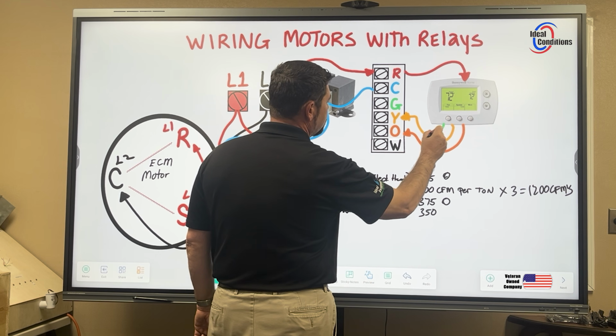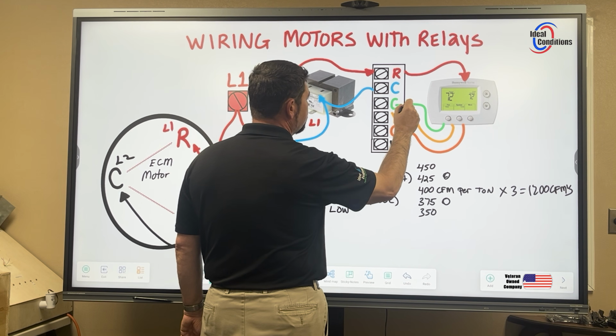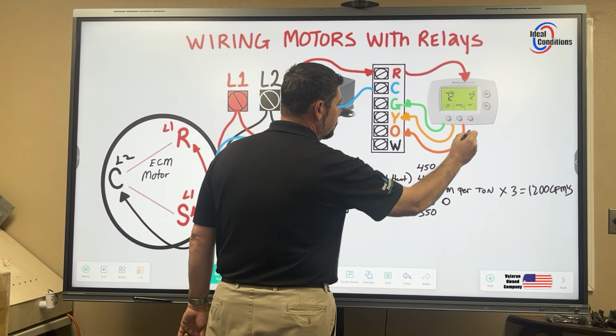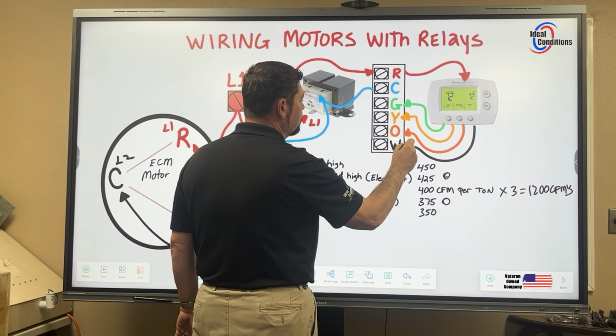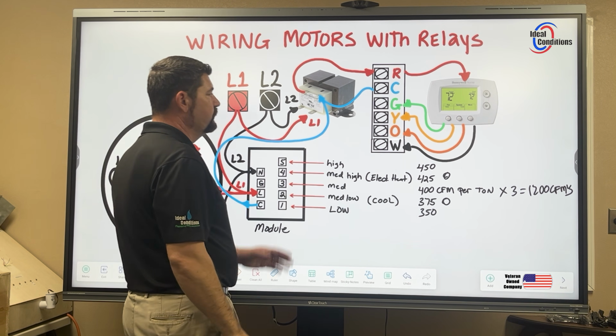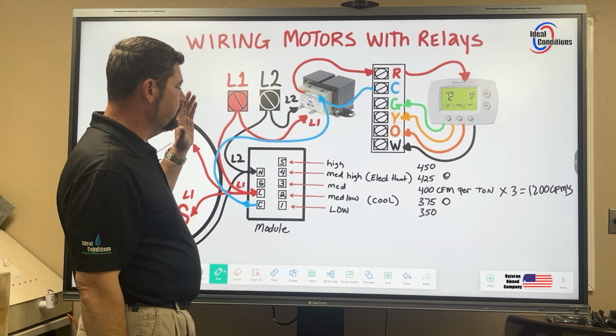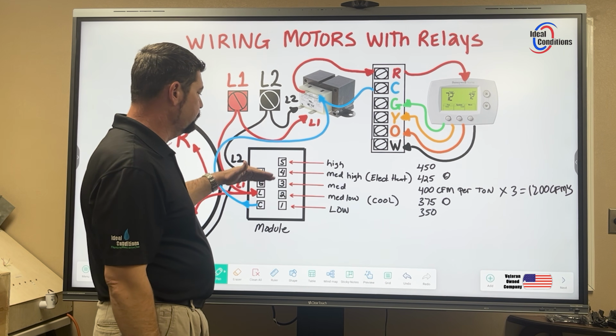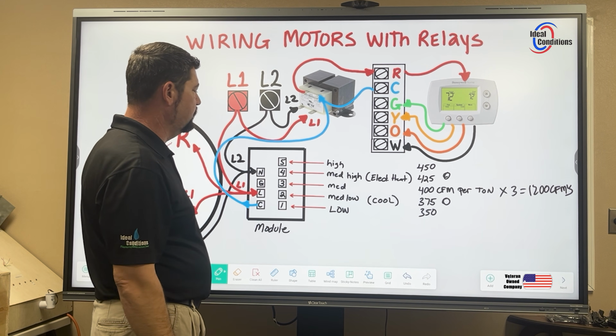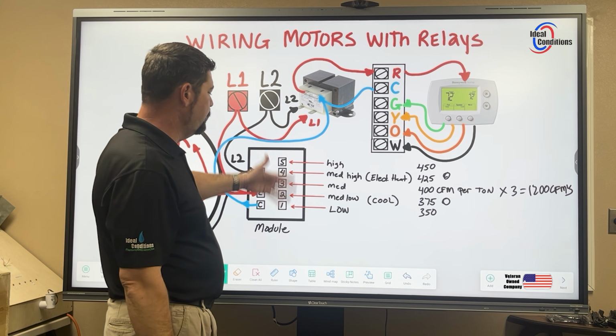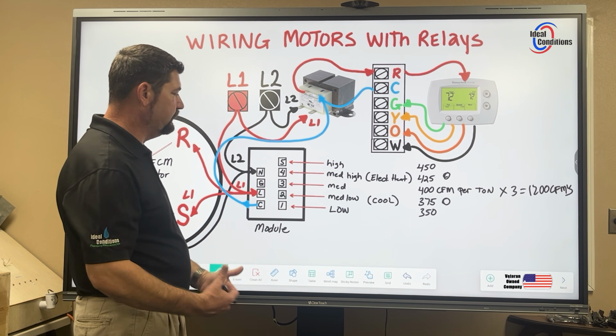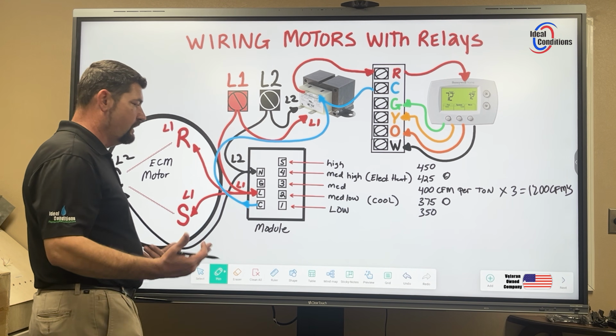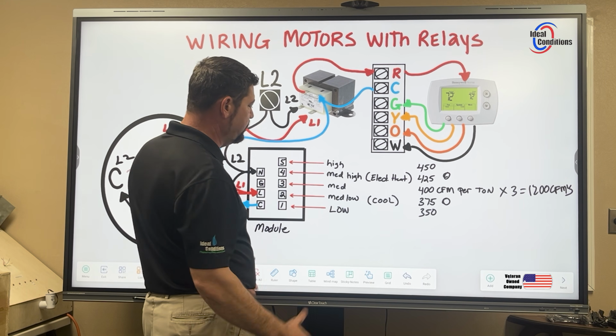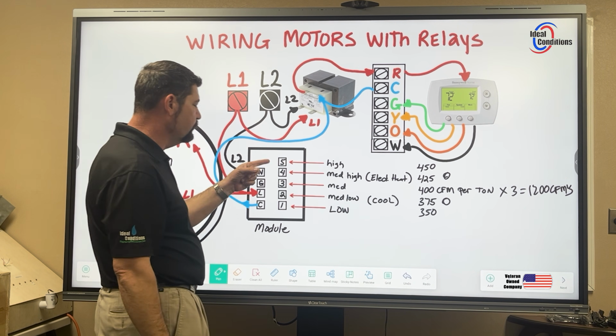The G call coming from the thermostat and the W call coming from the thermostat. Okay. G call's always going to come over here to typically your lower speed taps. It doesn't matter which two I wire up. Typically how you have it wired up, I'm going to wire it up that way, the way you would see from the factory, which is terminals 2 and 4.